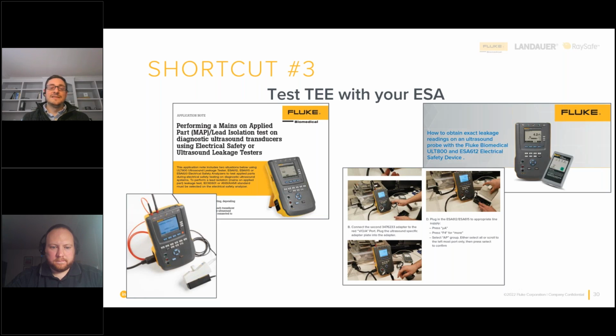The second extra usage for the ESA in terms of ultrasound is performing a mains on applied part test, or a lead isolation test, on diagnostic ultrasound transducers. This testing can be done with the transducer either attached to the ultrasound system or on the transducer itself when it's detached from the system, either for cleaning or disinfection. These are two great applications, and there are two great application notes to go along with this that will walk you through the step-by-step process in detail. But I did want to point these out to you today.